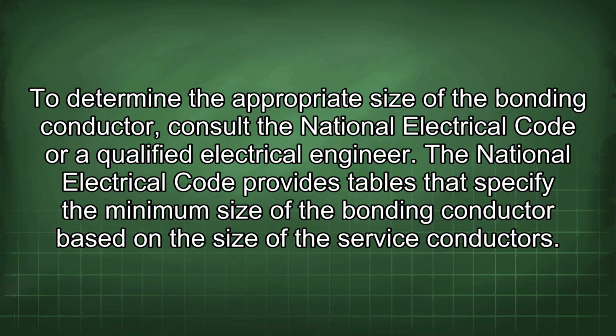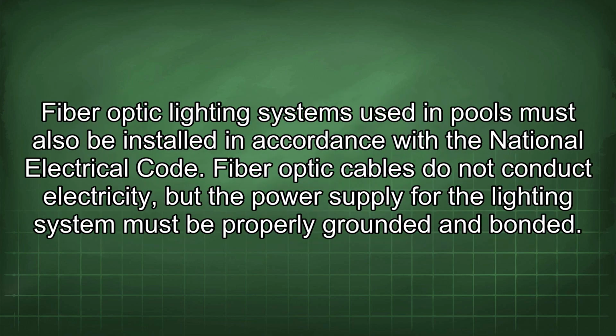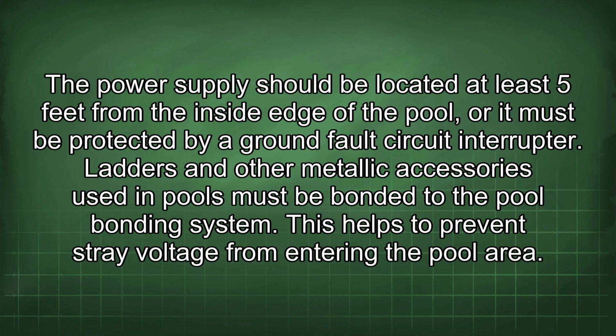Fiber optic lighting systems used in pools must also be installed in accordance with the National Electrical Code. Fiber optic cables do not conduct electricity, but the power supply for the lighting system must be properly grounded and bonded. The power supply should be located at least 5 feet from the inside edge of the pool, or it must be protected by a ground fault circuit interrupter.